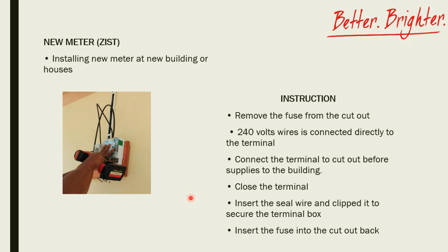Second is to remove the meter. We call it as ZRMQ. These are the reasons why we need to remove the meter. The instruction to remove the meter is easier than to install the new meter. We just need to remove the fuse from the cutout and then unscrew the connection of all terminal and remove all the terminal. At the end of the supply cable, we need to tape it out to secure the supply from exposing.